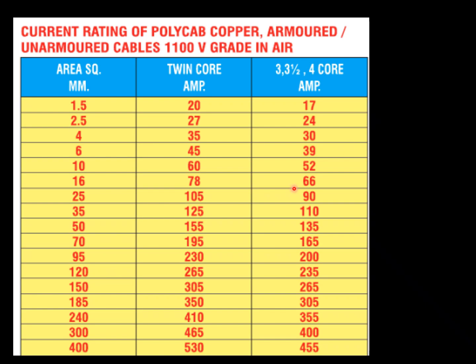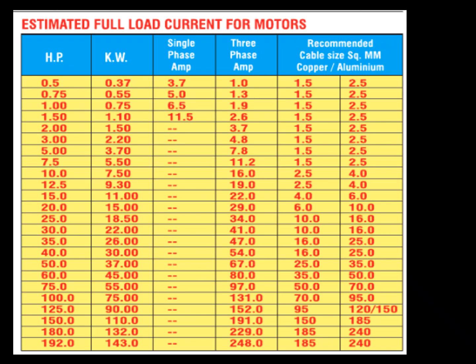This particular table shows you current rating of copper armored or unarmored cable up to 1100 volt grade in air. These are the amperes with respect to various sizes of cable. This chart is given by Polycab cables. Friends, quite often we deal with electrical motors, and this chart gives you estimated full load current for induction motors. When we say motor, it means induction motor for different horsepower or kilowatt rating. What will be the load current for different sizes?